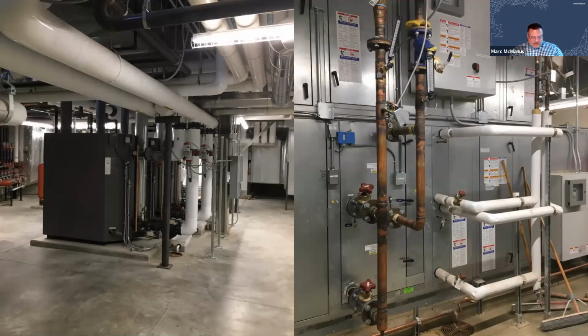We'll talk about that one a little bit later when we go into that room, but it uses an energy recovery loop. You're looking at 3 condensing water boilers, and the current technology, condensing water boilers, gas-fired, are about as good as you can get, especially for the price. The building is not large enough to need any sort of additional heat recovery or free cooling on the heating side. So there's 3 2500 MBH boilers, which allow for substantial turn down throughout the year.